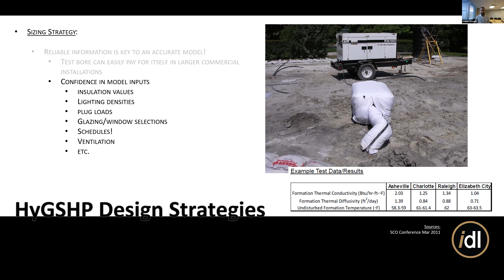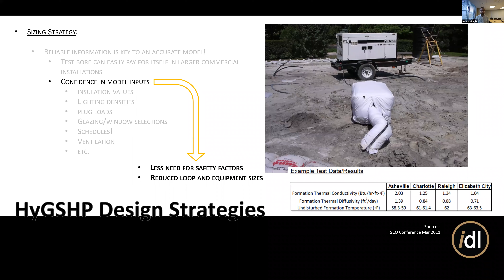The more work that's done on creating those models—this could be an energy model, or it could just be the engineering heat load model. It doesn't have to be a full-on EnergyPlus model, but as long as all of these factors are built into it, you don't have to worry about adding all those extra safety factors, and you can downsize your equipment. You might be able to downsize your pumps or reduce the flow so you're not trying to push as much water through all the time. There are a lot of tools out there, pretty specialized, and the more information you have on the site and the ground, the better. I highly recommend seeking out this expertise.